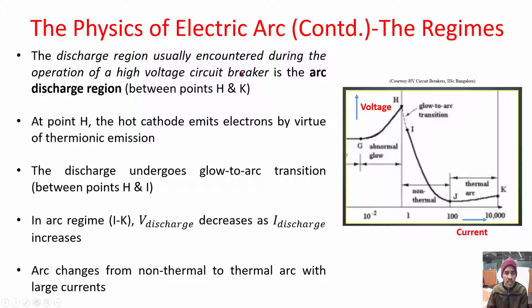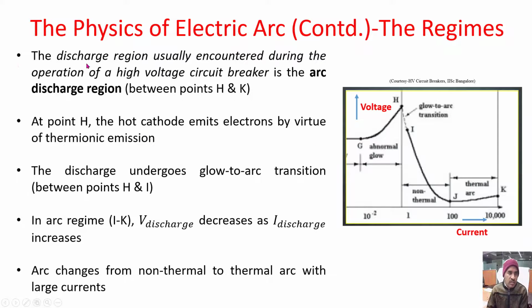Now, the discharge region usually encountered during the operation of a high voltage circuit breaker is this region. In this entire characteristic, we are interested in this region, the arc discharge region, between point H and point K. At point H, the hot cathode emits electrons by virtue of thermionic emission. So the discharge undergoes glow to arc transition. This is the glow region, this is the arc region, and from H to I it undergoes a transition.